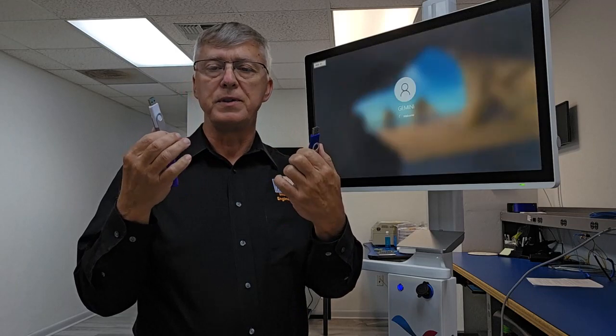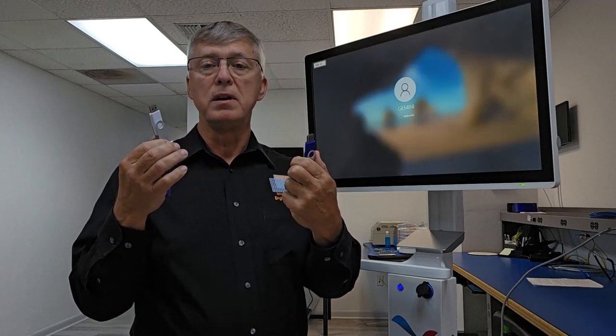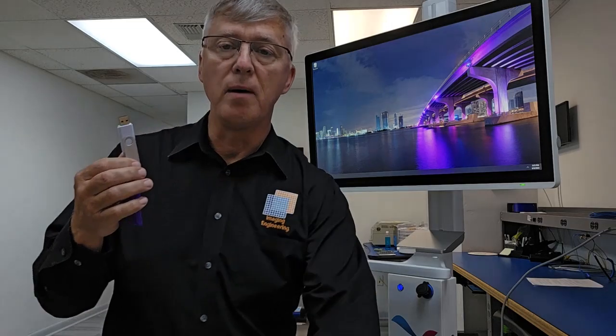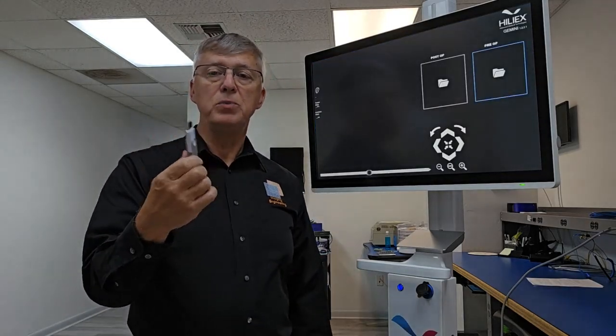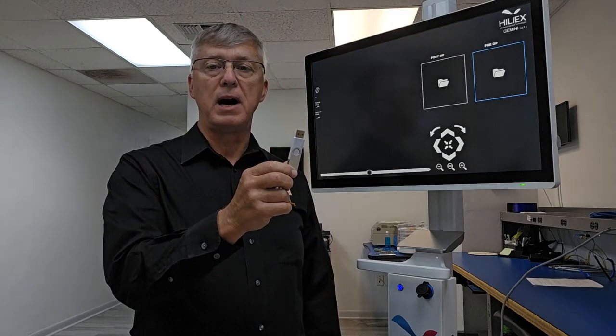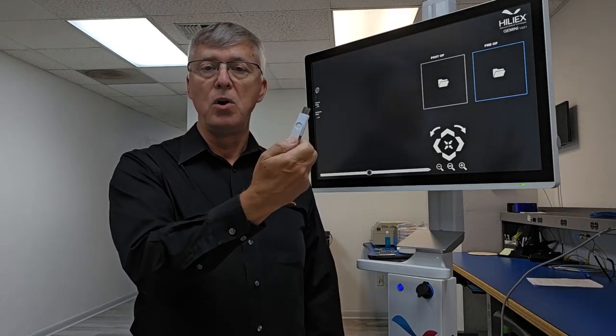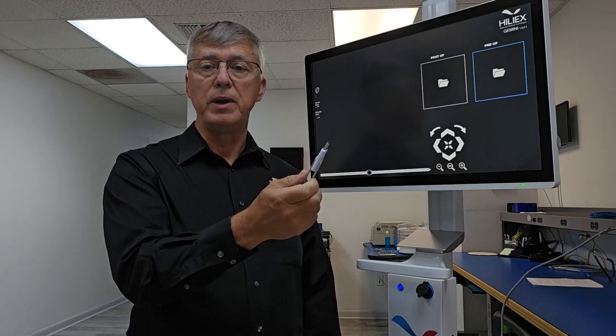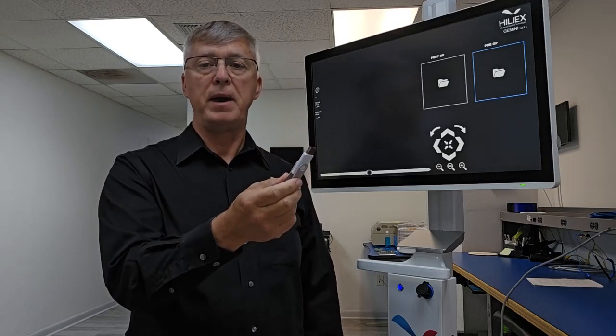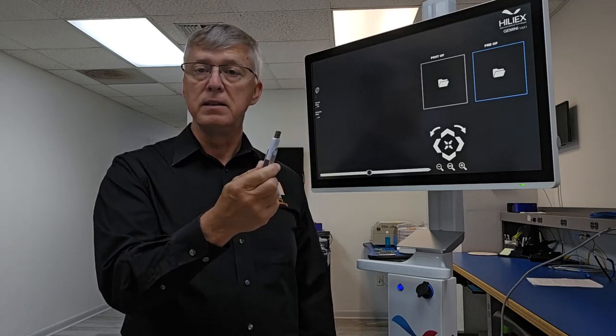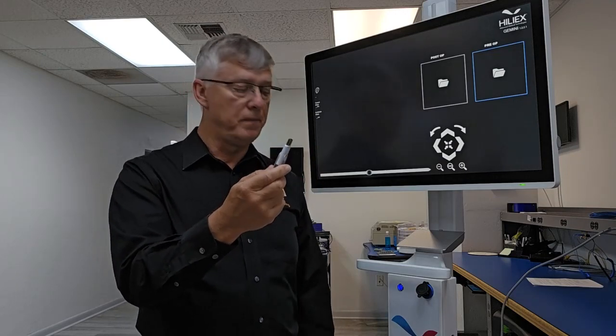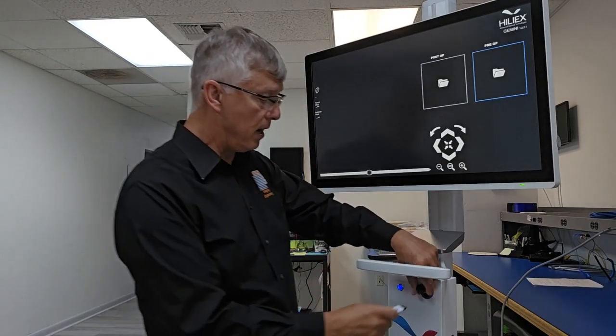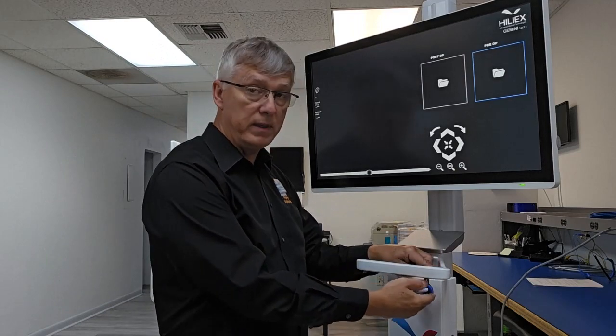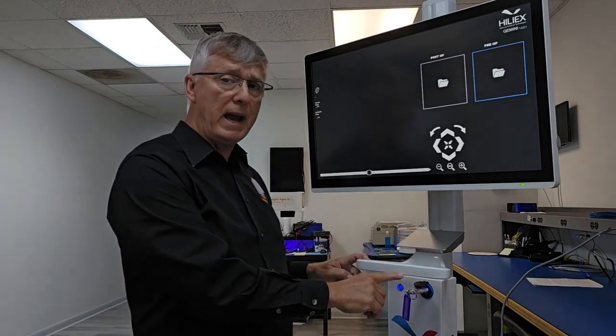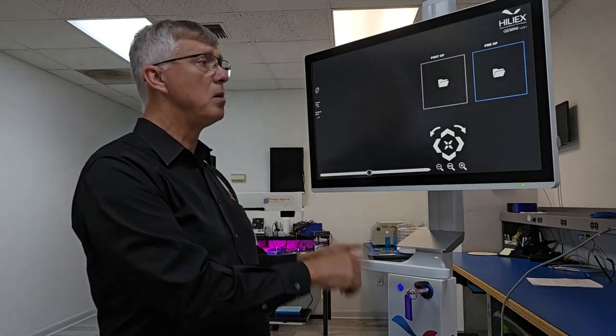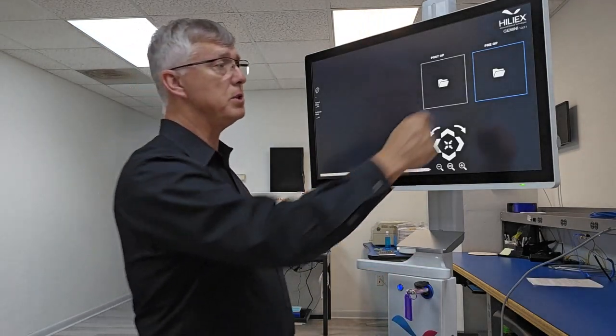The reason for 2, they're both the same thing, is in case you have 2 different C-arms that you're using in the OR. What we recommend is that you put on the pre-op and post-op or the affected and unaffected images on the USB using either the Sony printer, or if you have one of the newer flat panel C-arms that can send images direct to USB, you can use that method. All you have to do is take your USB and you plug it right into either one of these 2 ports. And you do want to have the USB plugged in first before loading your images.